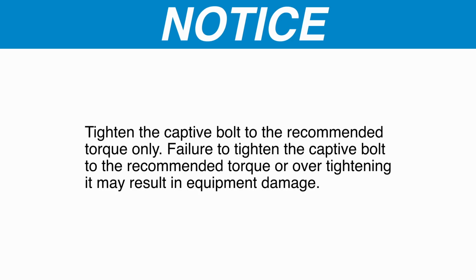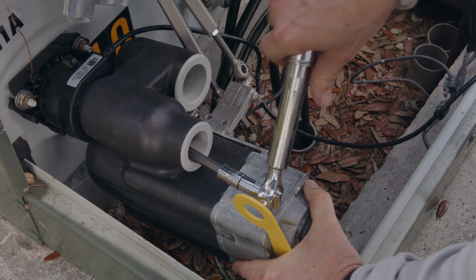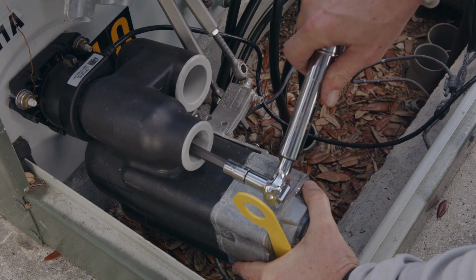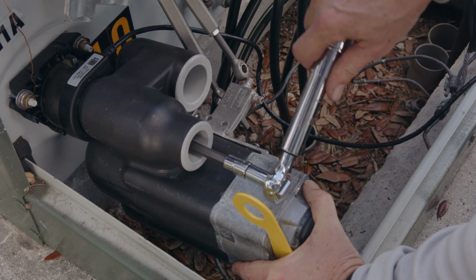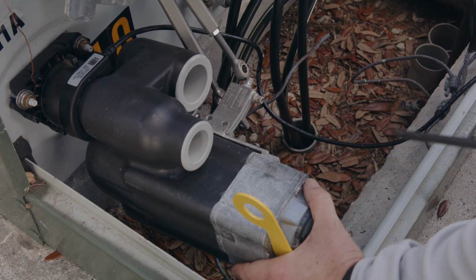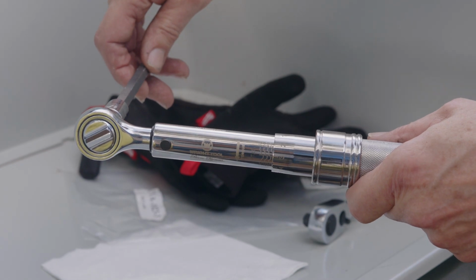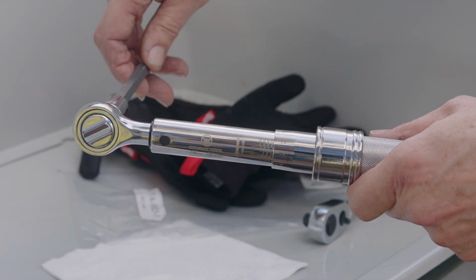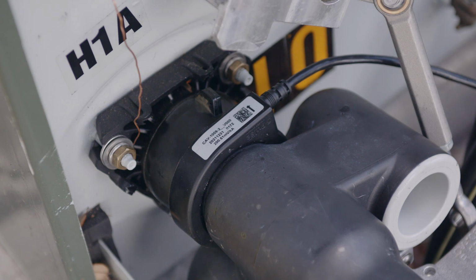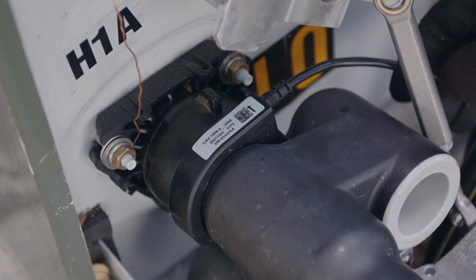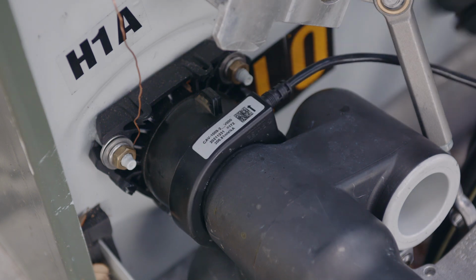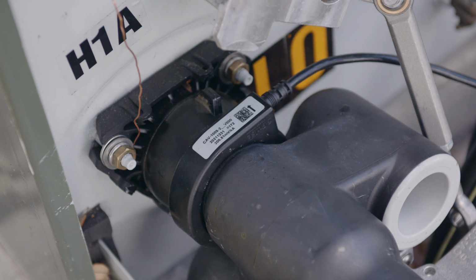Notice: tighten the captive bolt to the recommended torque only. Failure to tighten the captive bolt to the recommended torque or over-tightening it may result in equipment damage. Step 4. Tighten the captive bolt using a 3/8" long style Allen wrench to a torque of 23 ± 2 foot-pounds. Step 5. Rotate the current sensor so the writing is facing up and the flat side is horizontal with the wire going under the secondary terminals.